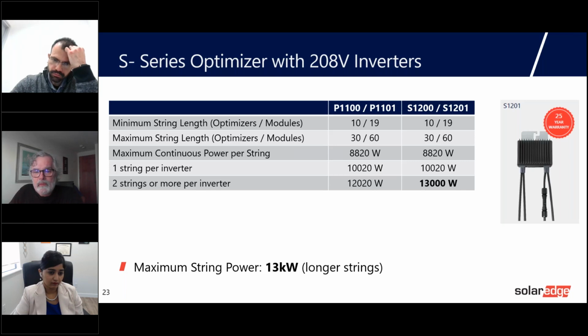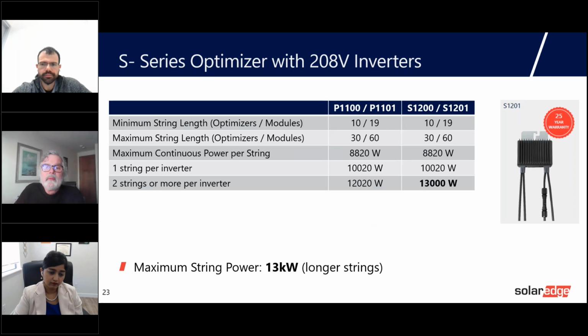And then the last row here is for two strings or more. With two strings here, we have enough DC power that now the inverter is actually going to be limiting current on the strings. So again, we won't actually approach the 18 amp maximum per string, because with two strings and this much DC power, the inverter maximum input current would actually be limiting current on the two strings. So in this scenario, we allow a lot more power per string than a single string design. So we allow a lot more string oversizing. And one of the advantages to the 1200 series is we do allow a bit more power per string than we do with the P1100, P1101. So we're up to 13 kilowatts per string with the S1200, 1201. Next slide, please.